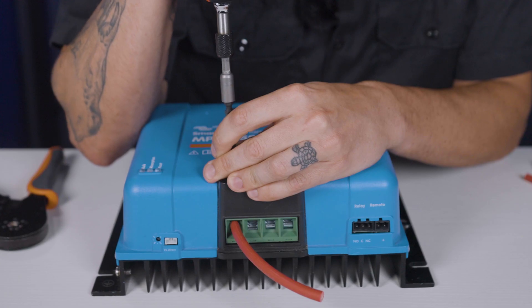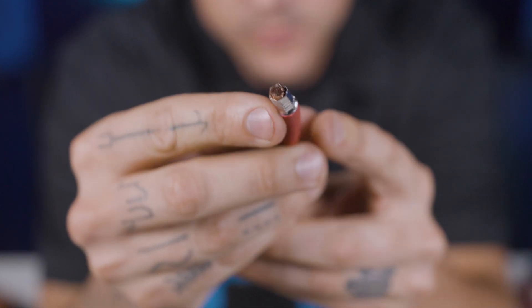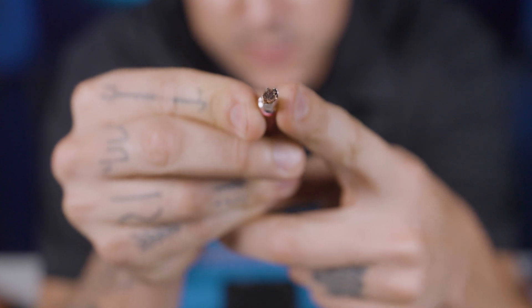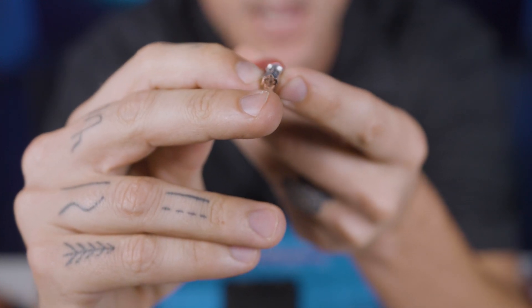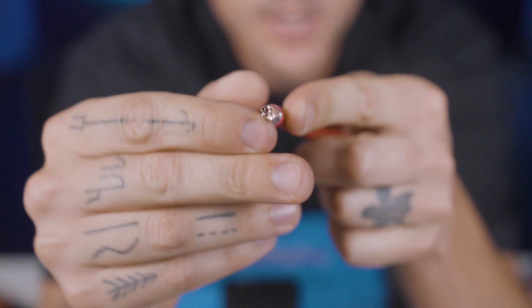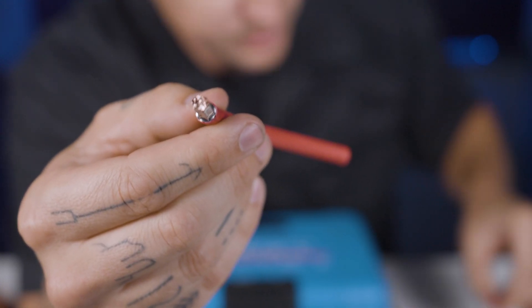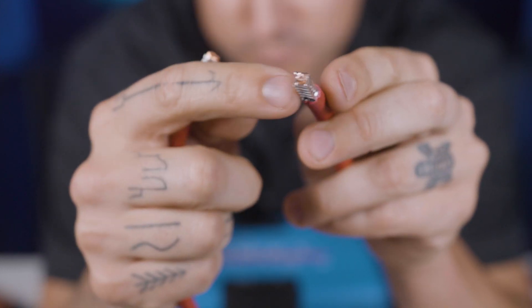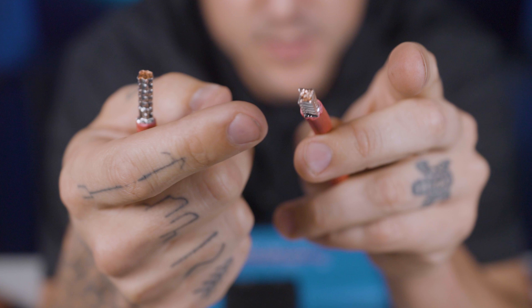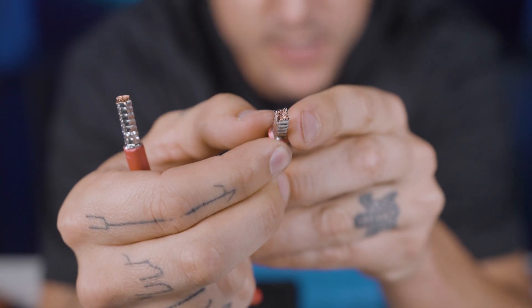Now I'm going to loosen it up. The ferrule end has flattened out just a little bit, specifically on all these little ridges, and made it so that there would probably be adequate connection there. This illustrates the fact that if you were to do this with a square terminal to start, it's going to yield even better results and you're going to have a great method of connection.